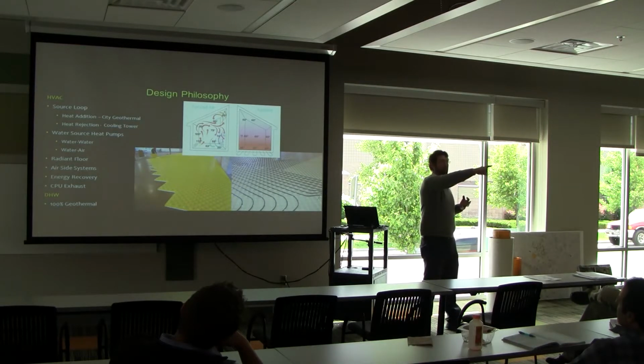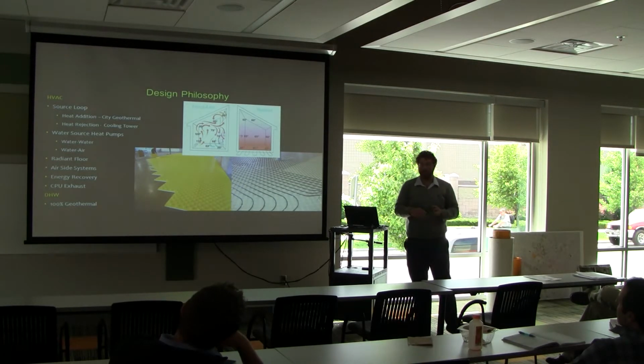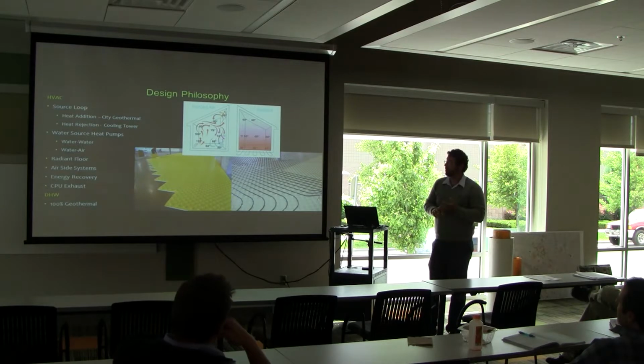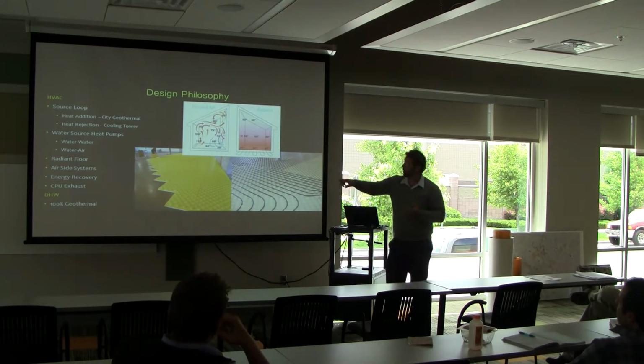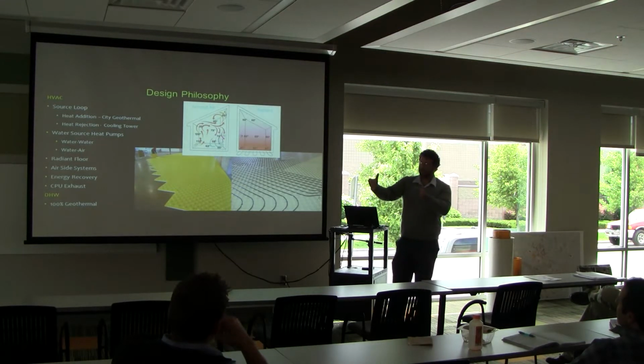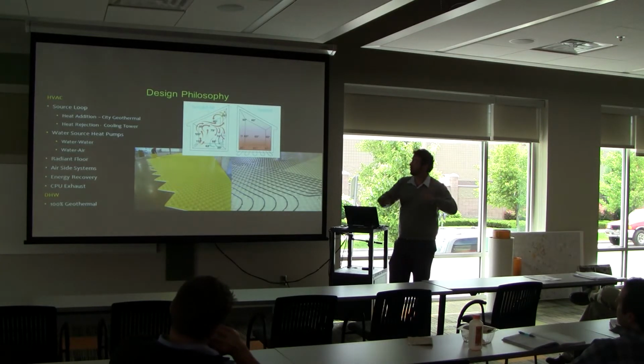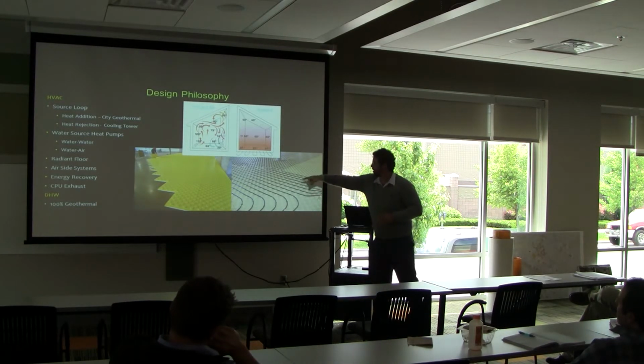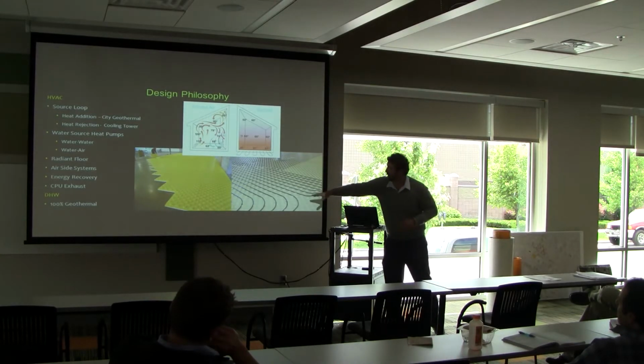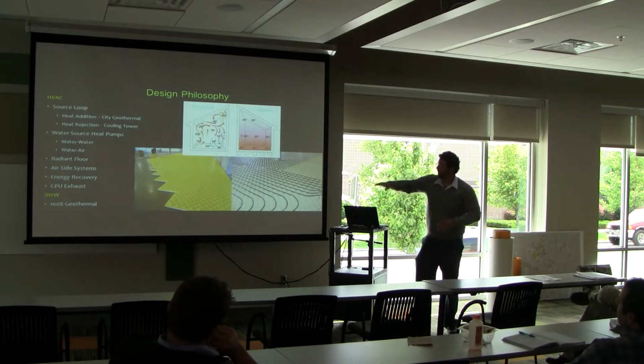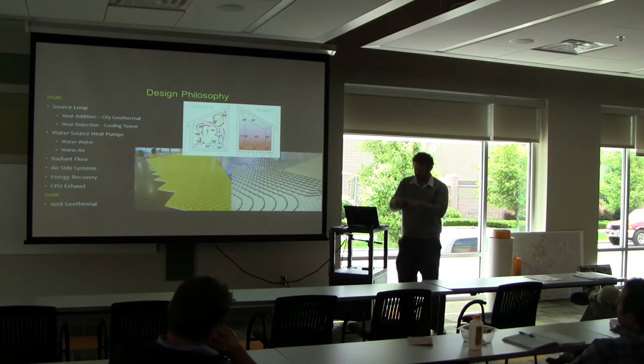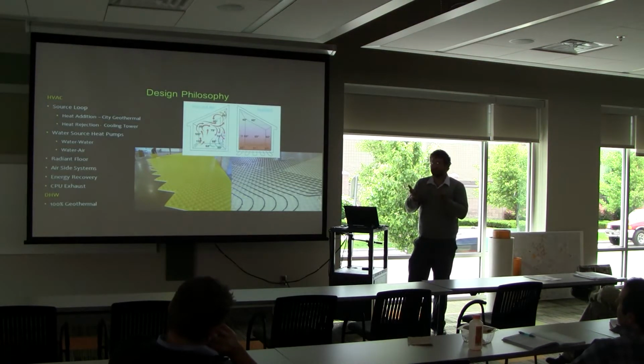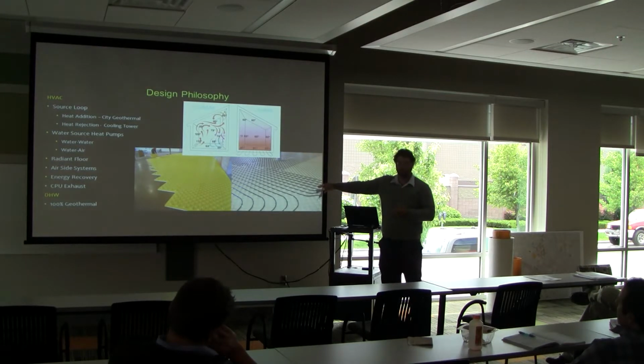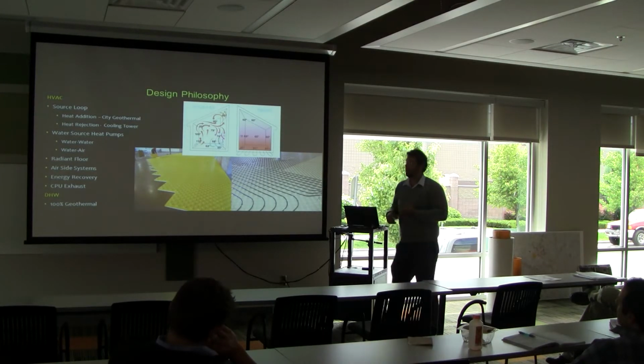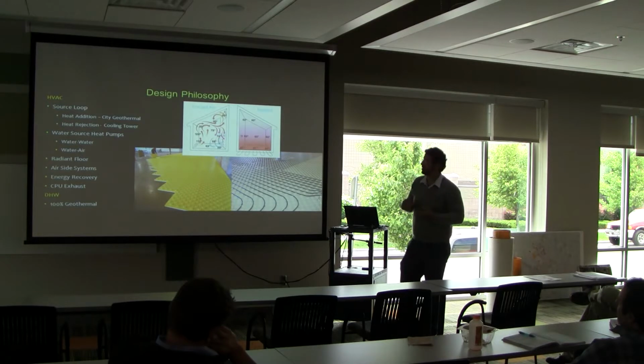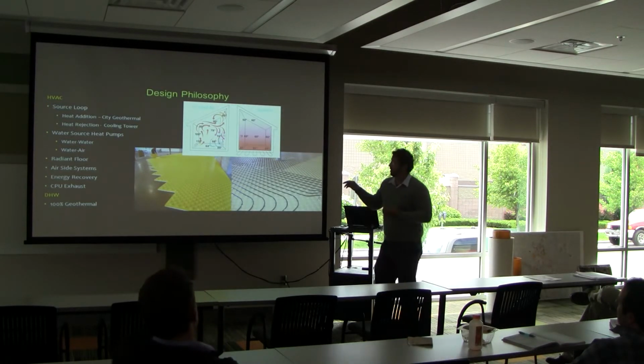The entire radiant floor, which is out in that big office area, is run off the water to water heat pumps. The water to water heat pumps, on the other side of the heat pump, not the side that's connected to the source loop, run about 105-degree water through this floor accordingly. The floor is insulated, kind of looks like Legos, but it's about 3 inches of insulation that sits below, so we're not losing heat down. Even though heat rises, we're still insulating it. There's literally miles and miles of this piping in that space over there. Russ has all the information on exactly how many miles, but it's quite a bit.